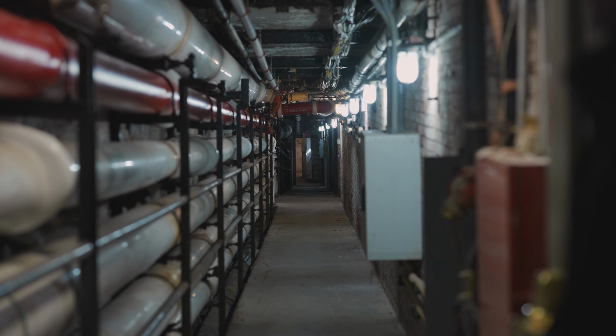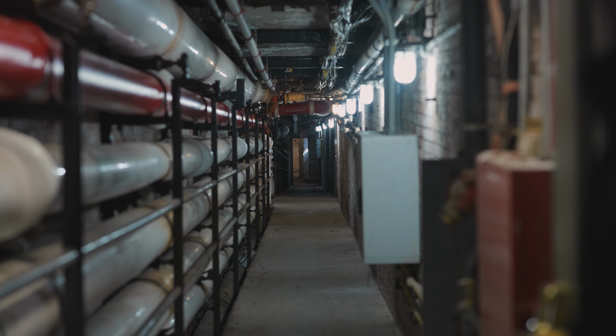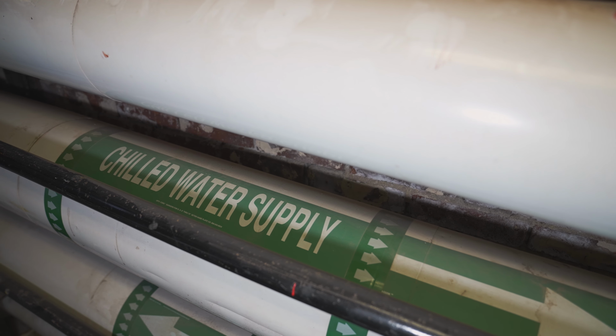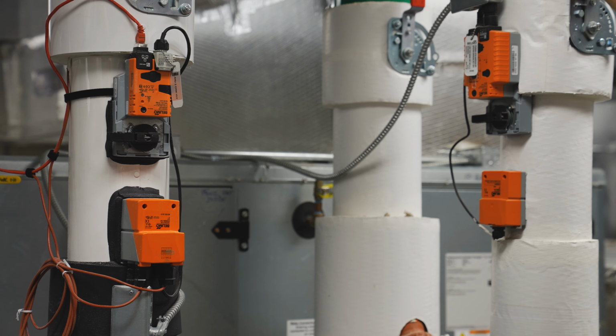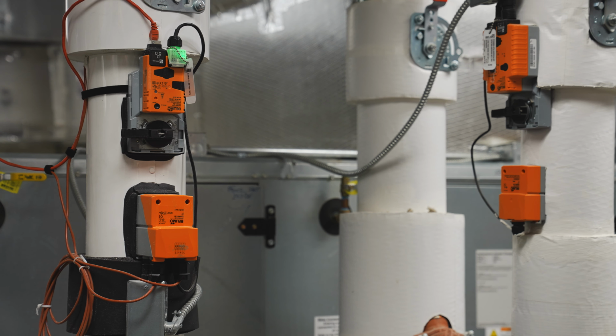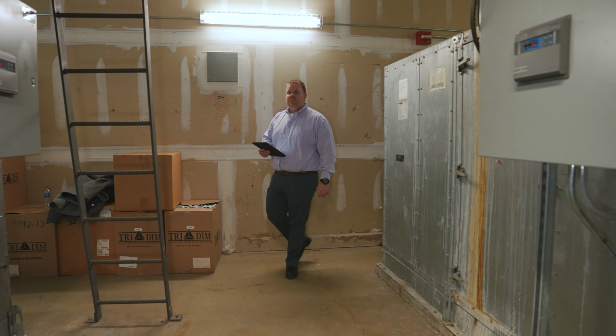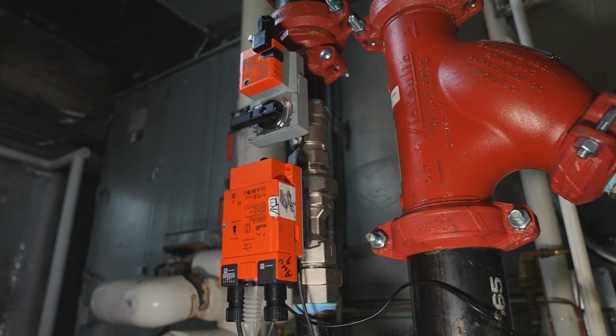Providence College is a utility-fed campus, so all their chilled water is coming from a central utility plant. The energy valve manages that delta T at the point of use, which maximizes dehumidification, increases the delta T at the piece of equipment, which then translates back to the central plant and optimizes the chiller performance.